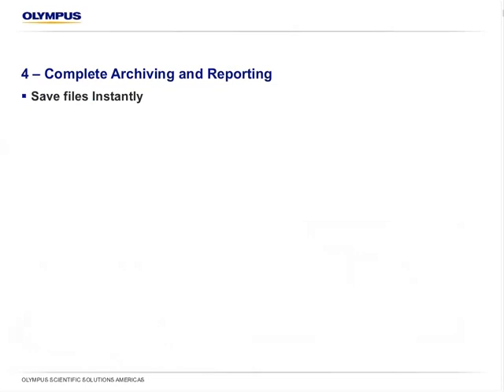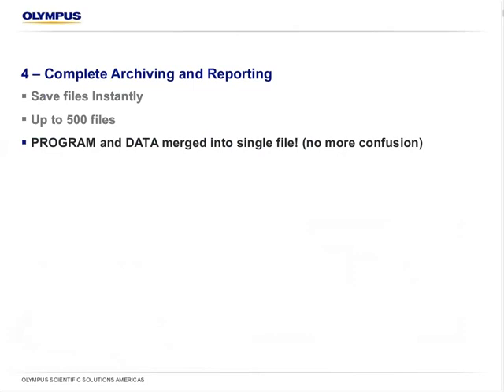One of the last improvements that are applicable to bolt hole or fastener hole inspection is complete archiving and reporting that comes with the NORTEC 600. Basically, you can save files instantly. Up to 500 files can be saved on the micro SD cards of the instrument. The programs or setups and data files are actually merged into single files. So I don't know how many times I've heard comment about hey, I thought I saved my file, but I can't find it because somebody saved the data file and thought they saved the program, or the opposite. So that's not happening anymore because there's only one file directory, and each file saves both the data and the program inside.